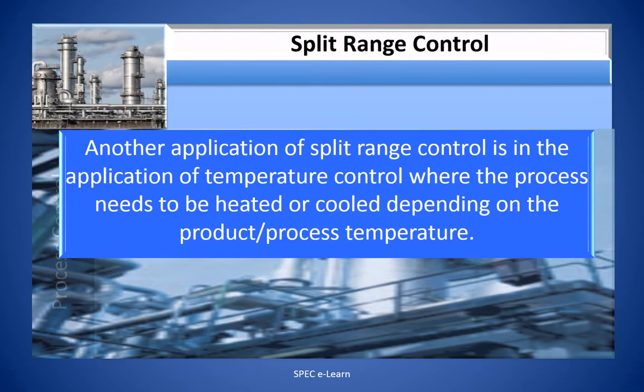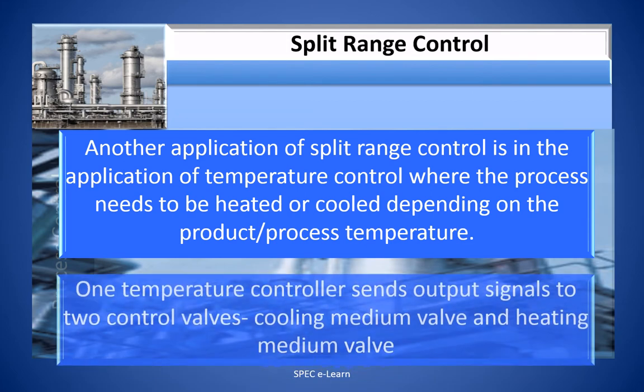Another application of split range control is temperature control, where the process needs to be heated or cooled depending on the product or process temperature. One temperature controller sends output signals to two control valves: a cooling medium valve and a heating medium valve. If the product has to be heated, the controller output signal will be such that the heating medium valve is open either 50% or 100%, while the cooling medium valve remains fully closed.